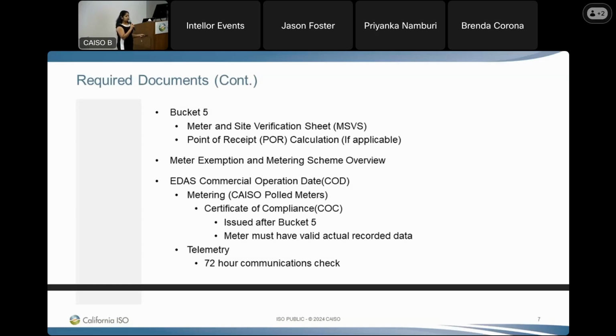So we check every single data point, all the analog data points, all the digital data points, and all the logical calculations for a 72-hour period. And we expect that the data is in good quality and we are getting the expected data in the calculations and the logic working accurately. So once that is met, we give the 72-hour approval. So I'll talk about that in detail in the next slides.